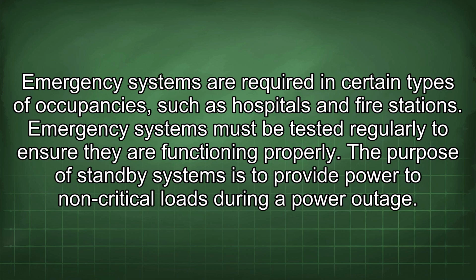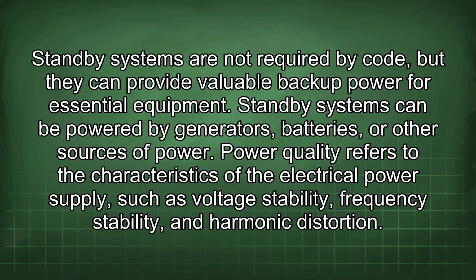The purpose of standby systems is to provide power to non-critical loads during a power outage. Standby systems are not required by code, but they can provide valuable backup power for essential equipment. Standby systems can be powered by generators, batteries, or other sources of power.